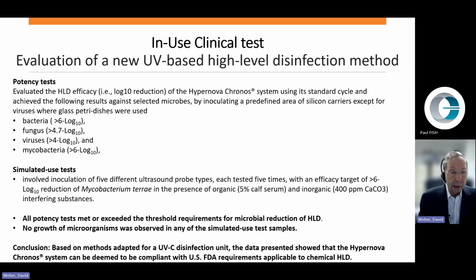And I should note the inorganic load and the organic load would correspond to failure to clean the device after use prior to high-level disinfection. Importantly, no growth of microorganisms was observed in any of the simulated use test samples. The conclusion, based on methods adopted for a UVC disinfection unit, the data presented show that Hypernova Chronos system can be deemed to be compliant with US FDA requirements applicable to chemical high-level disinfection.